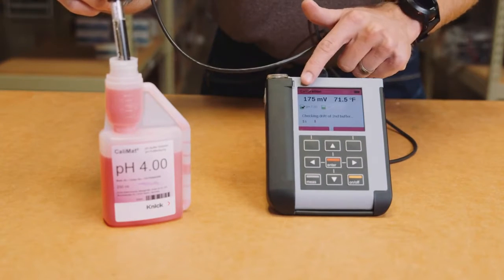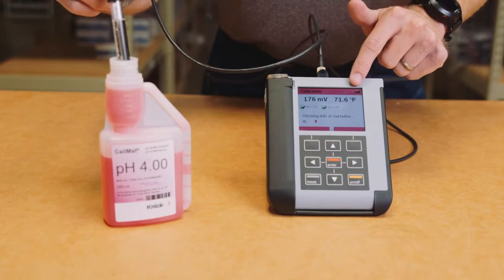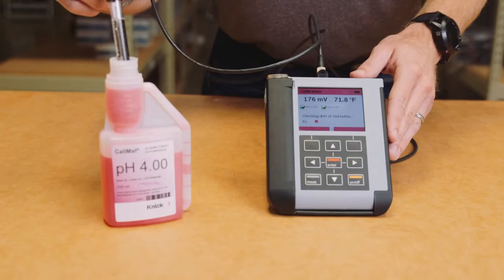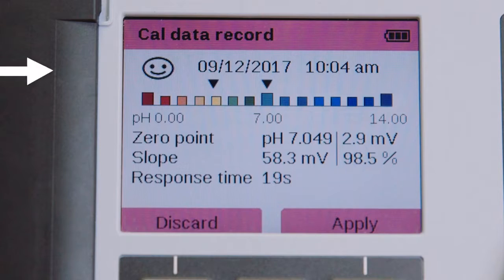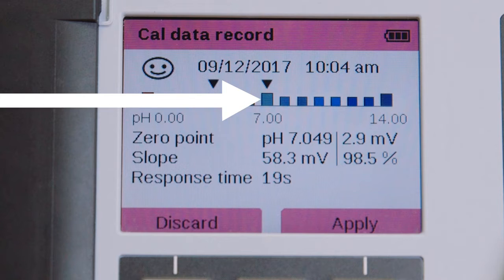The meter will now check the drift of the second buffer, automatically indicating its value and again displaying the millivolt and temperature. Once the process is finalized, you can see that the Portavo provides a summary of the results of the calibration. In the top left corner, there is a smiley face indicating that our calibration is good. The specific values of the calibration are also indicated: the 0 point, the slope, and also the response time of our sensor. Finally, there is a pictograph above these values indicating the 2 points that we used during our calibration procedure. Here you can see the arrows indicating the buffer values of 4 and 7 that were used.